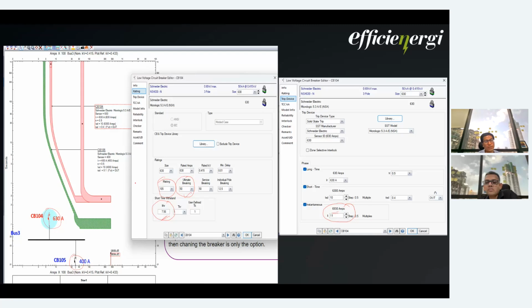So this is the reason we said this coordination is wrong, because it has to have the instantaneous regions overlapped on each other. If you see the difference, earlier it was 4800 ampere and here it is 6900. So definitely both breakers will trip simultaneously on any fault of more than 4800 ampere, and not 6900 ampere.